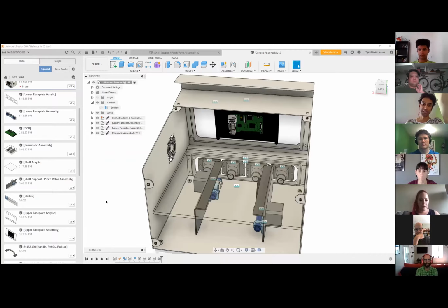And then there's a vibe test going up to 500 hertz for 10 minutes per axis. The acceptance criteria is usually that basic safety and essential performance are not compromised. That means nothing happens to the device that compromises the usage of this device, and nothing compromises its effectiveness at continuing to perform. What I still need to look at is whether those tests are done while the device is on or not, and I'm pretty sure it's not done during operation.